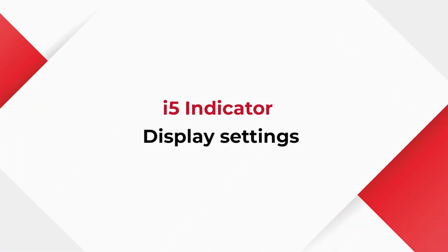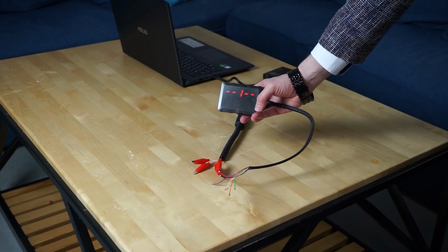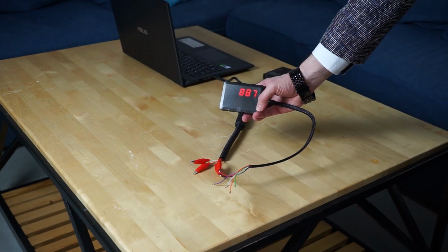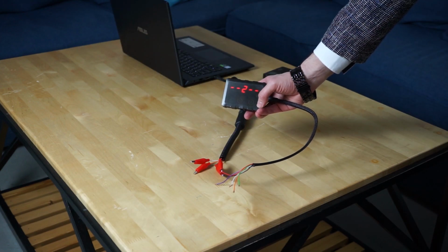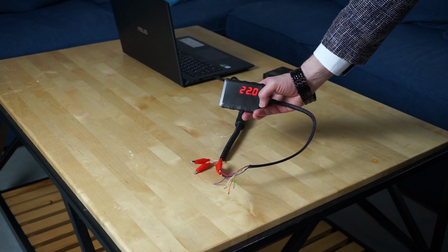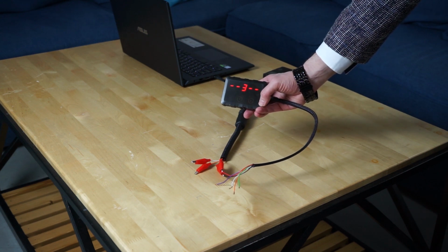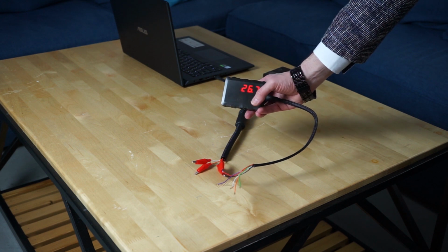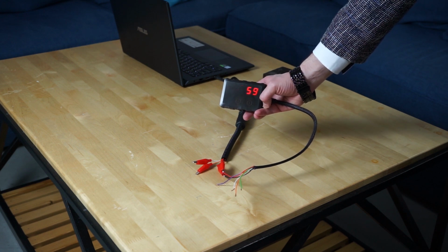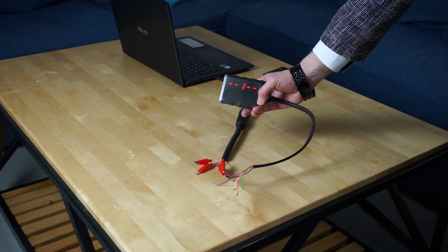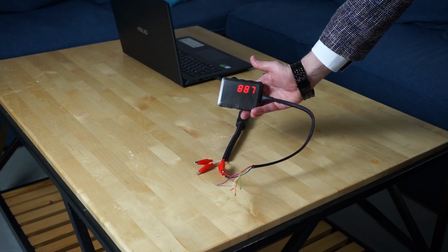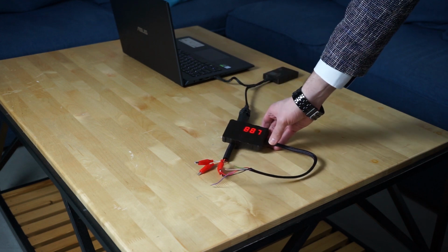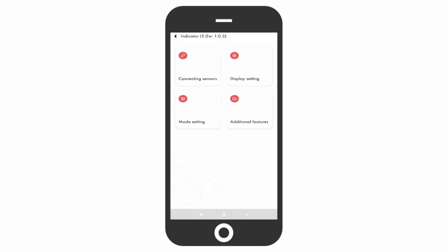Data View Settings, Virtual Windows Configuration. Since the i5 has only one display, but up to 10 sensors can be paired with it, there are 10 virtual windows that are displayed on the screen one by one. To switch between them, press on one of the indicator's buttons. Every virtual window can be used to display one parameter readings of a particular sensor.